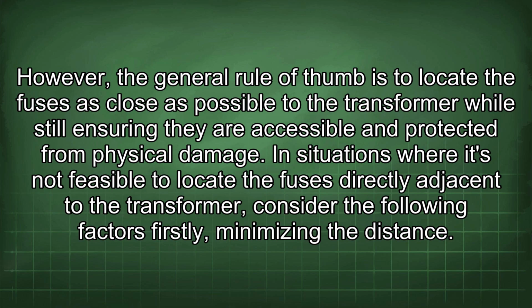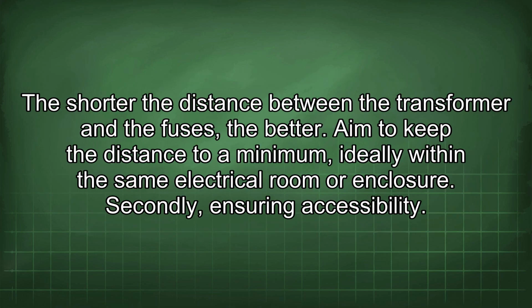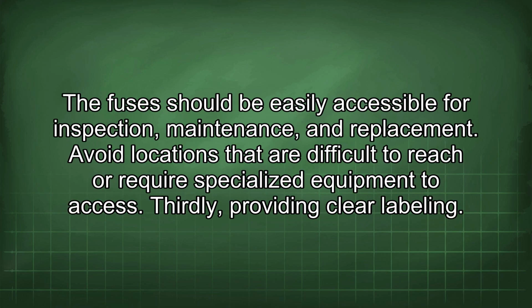In situations where it's not feasible to locate the fuses directly adjacent to the transformer, consider the following factors. Firstly, minimizing the distance. The shorter the distance between the transformer and the fuses, the better. Aim to keep the distance to a minimum, ideally within the same electrical room or enclosure. Secondly, ensuring accessibility. The fuses should be easily accessible for inspection, maintenance, and replacement. Avoid locations that are difficult to reach or require specialized equipment to access.